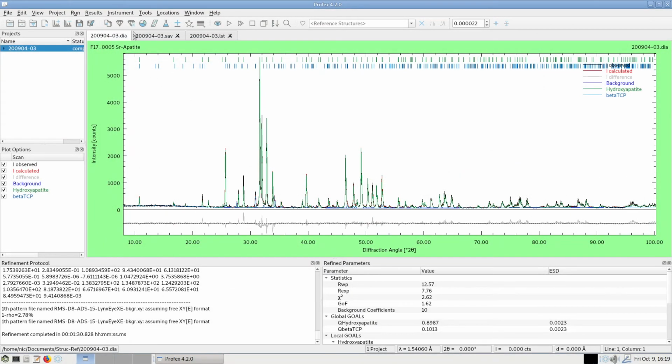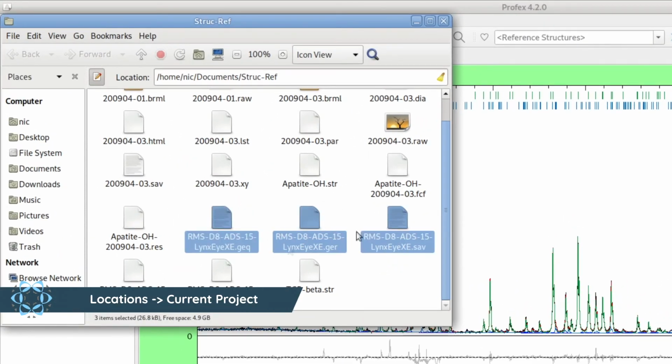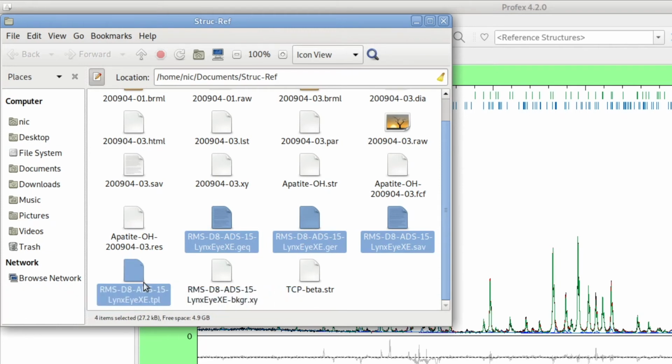We only edited our current instrument configuration file when we selected instrument, edit current FPA configuration. So this means we edited the local copy in this project folder and not the one in the instrument repository. So if we go to locations, current project, we find four files for our current instrument configuration. These are the ones that are extended up to 150 degrees 2theta now, but they are only stored inside the project directory.